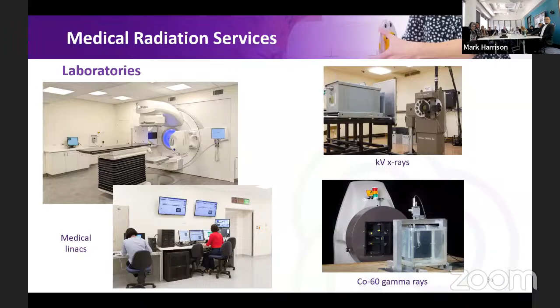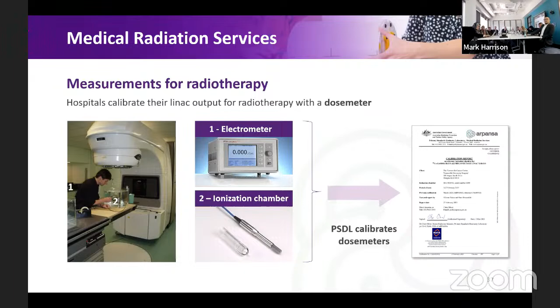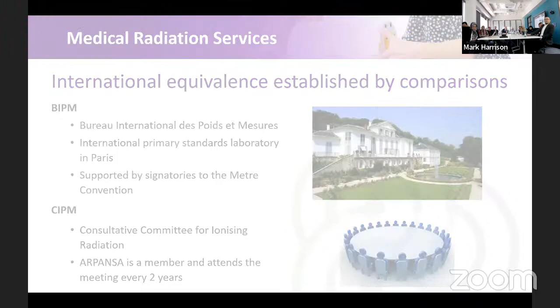So the facility sends in the ionizing chamber for calibration. It's calibrated by the team. We also calibrate the electrometer, and we end up with a dosimetry calibration sheet on the right there, and that's all NATA certified. We ensure that our primary standard is working appropriately by frequent formal comparisons through BIPM and CIPM, but we also conduct a number of informal comparisons with secondary standards and laboratory standards laboratories around the world.